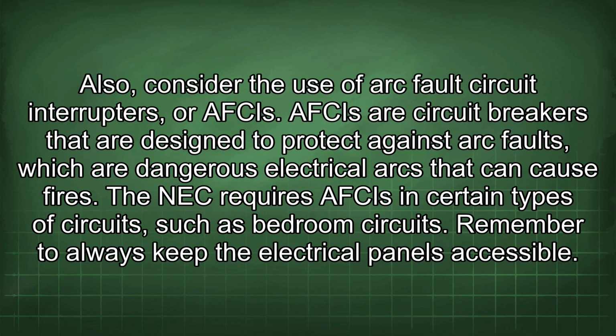Also, consider the use of arc fault circuit interrupters, or AFCIs. AFCIs are circuit breakers that are designed to protect against arc faults, which are dangerous electrical arcs that can cause fires. The NEC requires AFCIs in certain types of circuits, such as bedroom circuits.